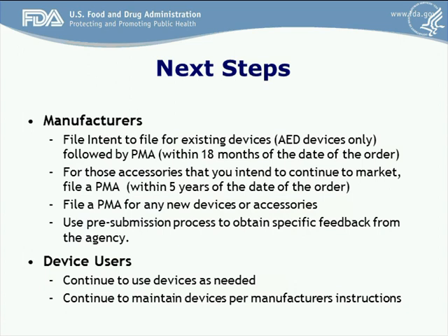So next steps for manufacturers: you need to file an intent to file for existing devices, followed by a PMA. It's important to remember that the intent to file is only for AED devices. For AED accessories that you intend to continue to market, you need to file a PMA within 5 years. For any new device or accessory that is not cleared through the 510K process, you need to file a PMA.